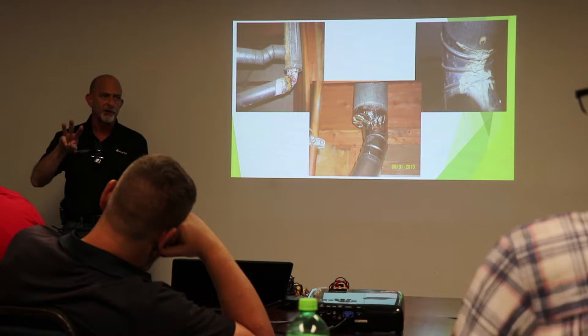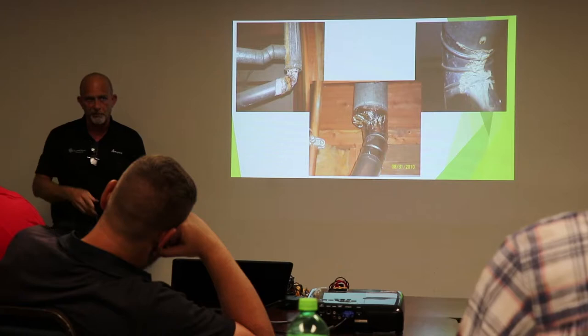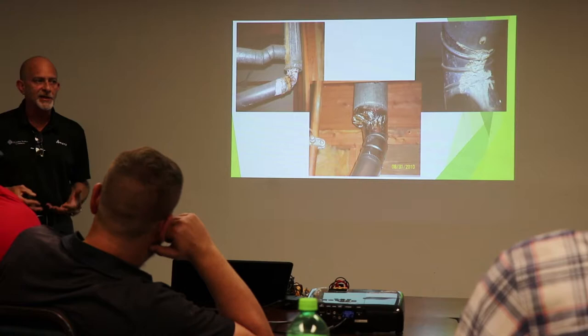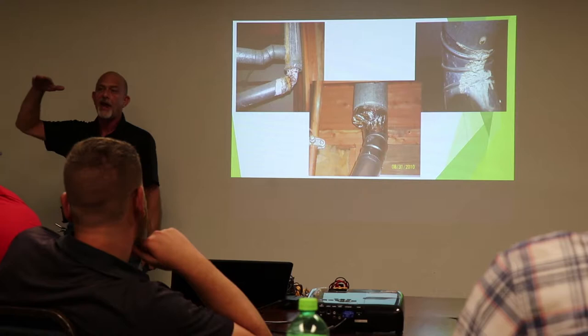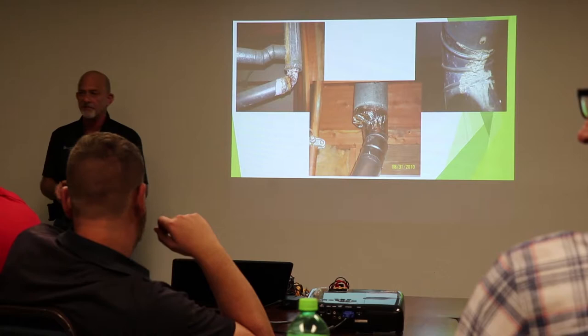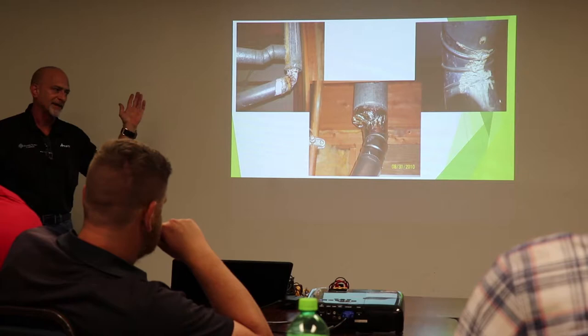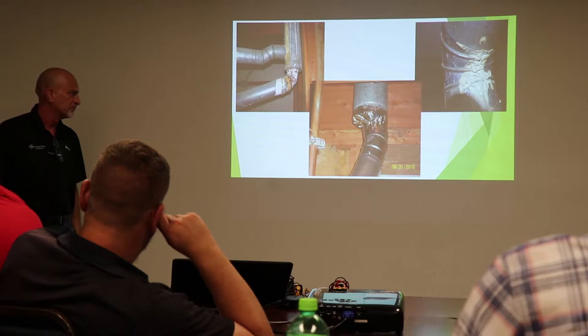J-hooks are cheap, right? If you're using J-hooks, in most cases, support, nail, or screw. Everybody uses screws now. But it's quick and easy when you're doing it, especially maybe on a repair. Maybe you guys didn't put that furnace in, and you go there and you see a big sag in your PVC. It's easier to do when the basement isn't finished. I agree with you with that 100%. When you're above drywall, you can't see it. But if it's an unfinished basement and you're running along joists, it's easy, especially to tack up another J-hook and bring it back up to where it needs to be.